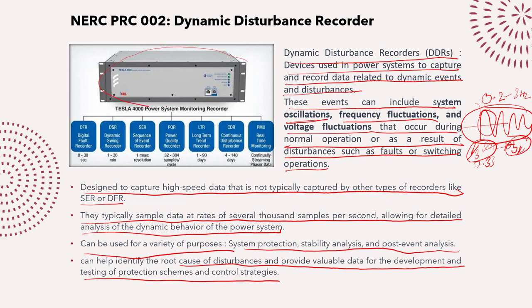A modern single recorder device can now perform the functions of multiple instruments: digital fault recording (files of 0–30 seconds), dynamic swing recording (1–30 minutes), sequential event recording at 1 ms resolution, power quality sampling, long-term SCADA-type recording, continuous disturbance recording, and PMU functionality. Advances in computing power and recording technology have enabled one single device to range from PMU and fault recorder to sequential event recorder, DDR, power quality monitor, and long-term SCADA recording.